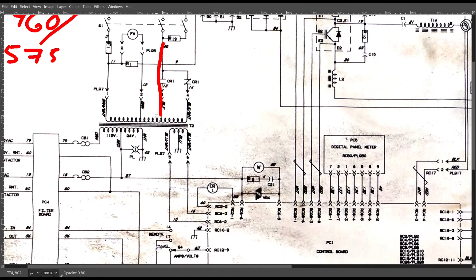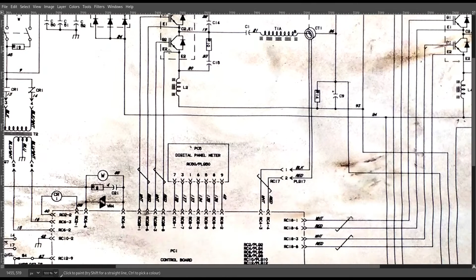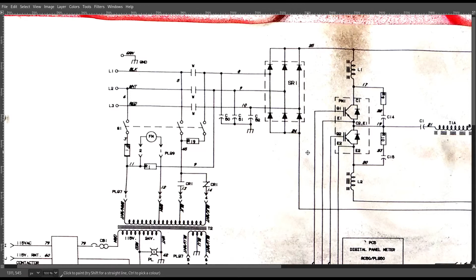Troubleshooting a machine like this, that's designed to run on pretty high voltages, is quite dangerous and a bit tricky, because you can't just go feeding 600 volts and hope that everything works. If something doesn't work, like let's say the control board is energizing both IGBTs at the same time, here you just short out the whole thing and that'll destroy absolutely everything in its path. Both IGBTs are going to die, the bridge rectifier is going to die, probably long before your disconnect here, which is hopefully fused or at least breakers. Before that opens, you'll already have caused damage.